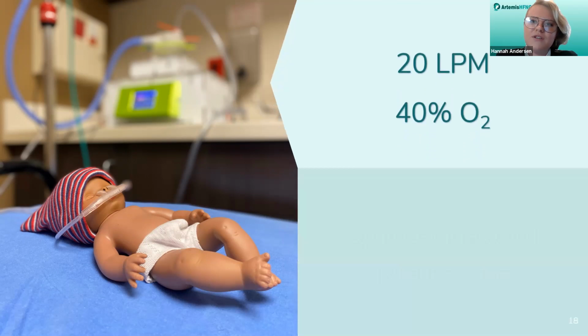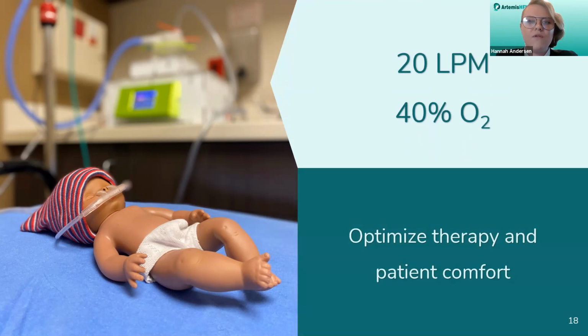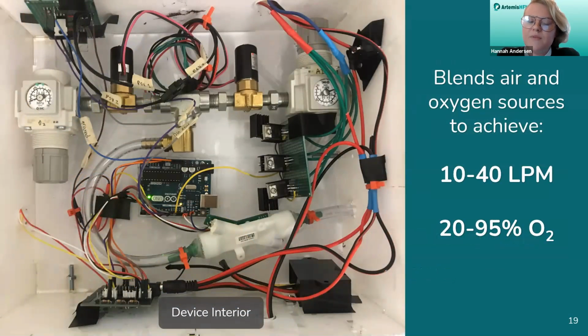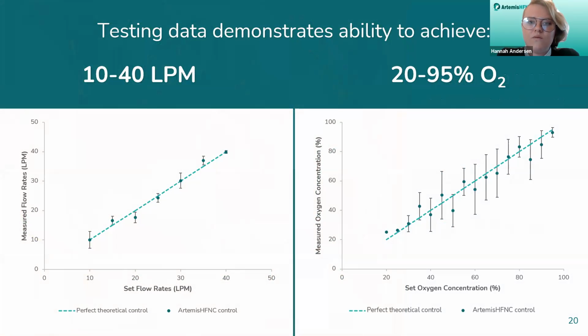So by allowing the clinician to adjust these parameters, they have full control over the air delivered to the patient, and they can change it at any time to optimize the patient therapy and patient comfort. So the device adjusts the prescribed flow and oxygen levels through the blending subsystem. This system blends room air and supplemental oxygen to generate high flows at controllable rates from 10 to 40 liters per minute and 20 to 95% oxygen. So as you can see here, we validated that our device can robustly control the flow from 10 to 40 LPM and 20 to 95% O2.